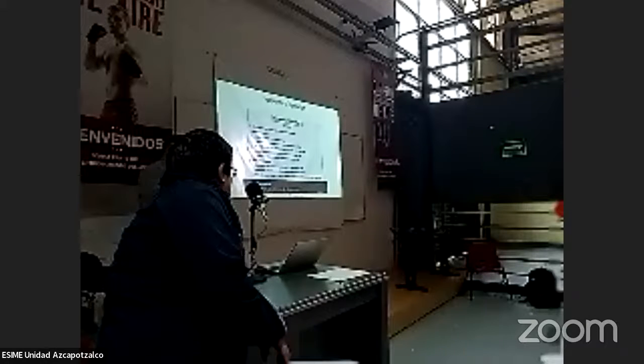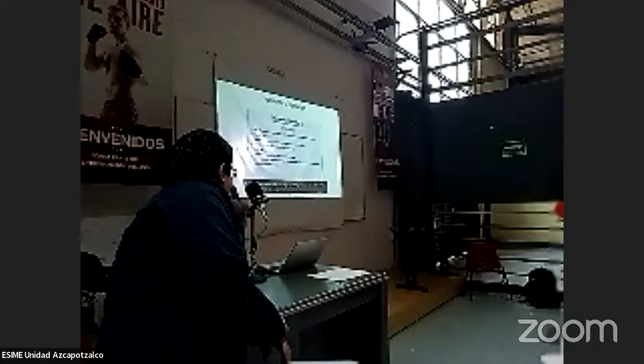Okay. Something else that it does before that happens is it will go into what we call an oil return sequence, which lasts about 6 minutes. Okay. So it may stay in that defrost another 6 minutes in order to make sure all the oil got returned back to the compressor. Okay. So that's how you know, if it terminates at more than 60 degrees, it could be doing an oil return. All right, the heat ends during a defrost.